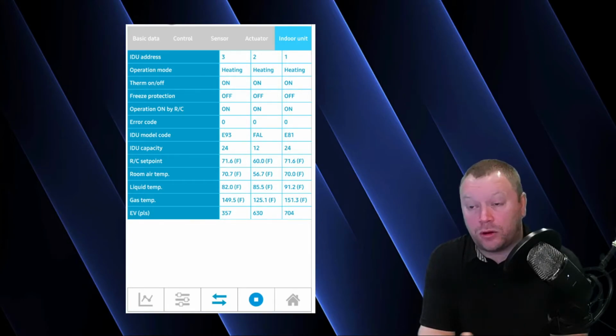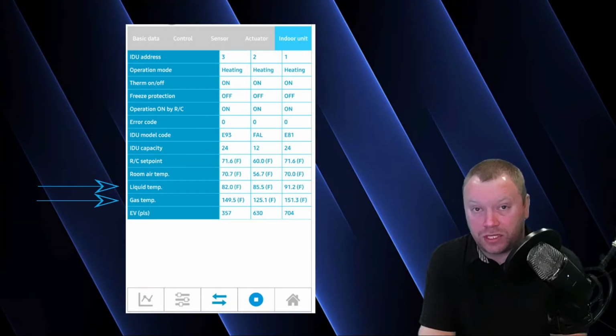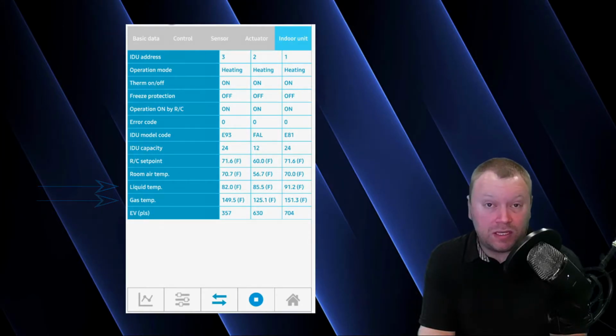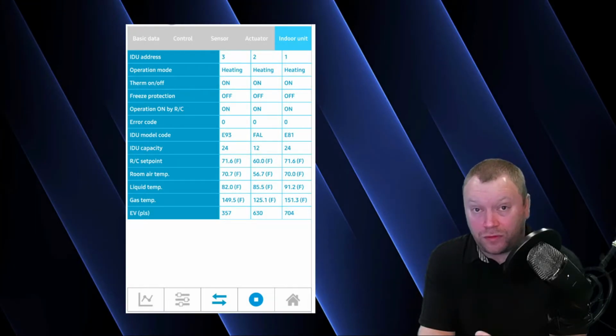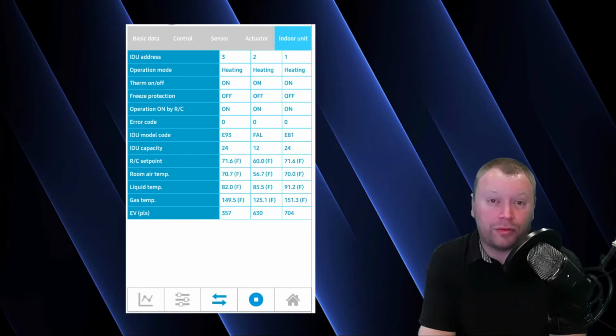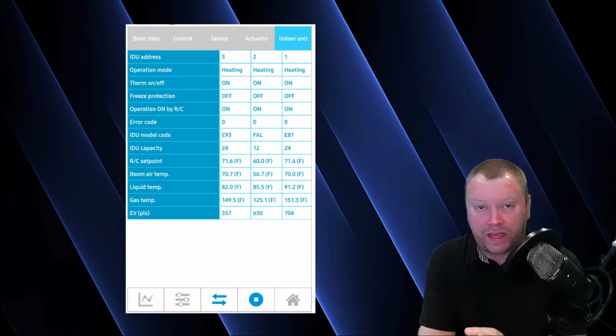You're also going to see that there is both a gas and liquid temperature sensor. And this is very advantageous for refrigerant temperature control compared to the mini splits. Mini splits only have one thermistor at the heat exchanger. We can actually look at the gas temperature coming from the outdoor unit, coming into the indoor unit heat exchanger, and the liquid temperature that's leaving the indoor unit heat exchanger. This gives us all kinds of control.